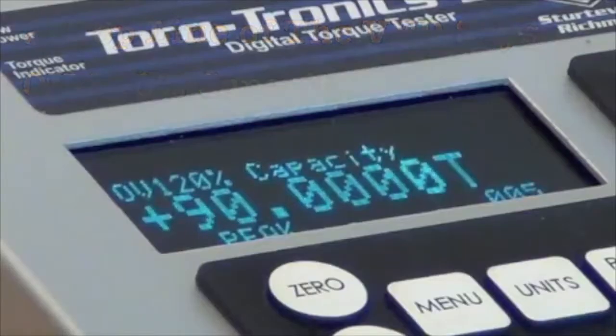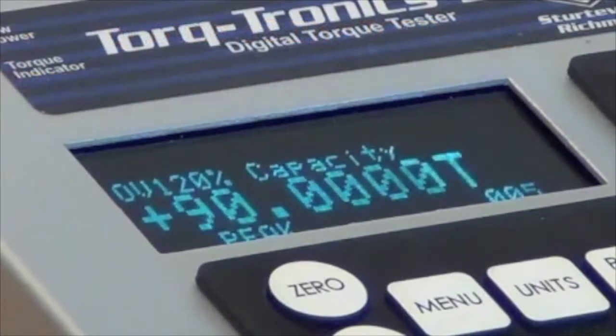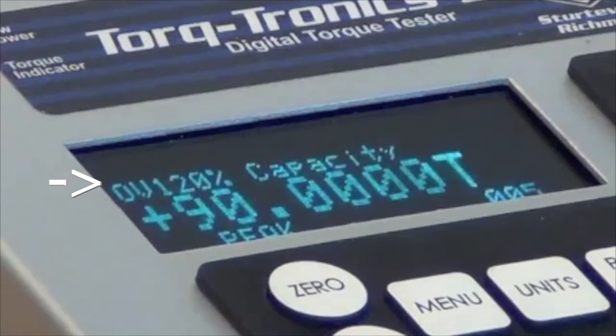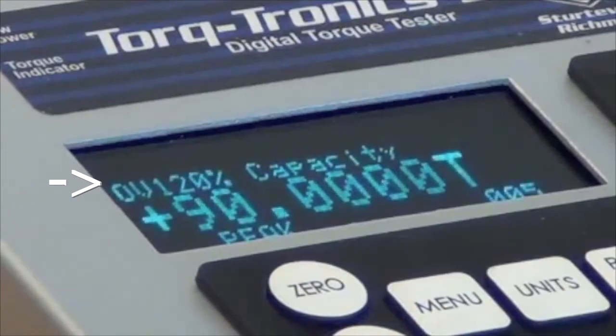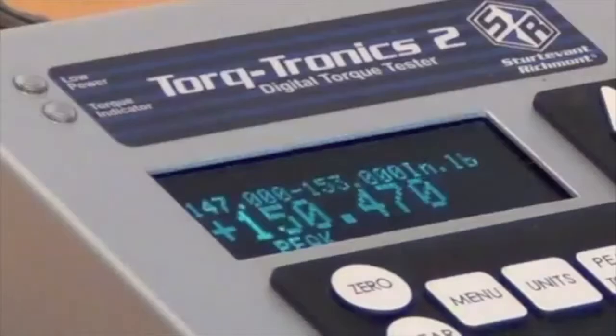If you try and test and calibrate tools between an overload event and resetting the overload flag, you'll notice a couple of things. First, the upper line of the tester display says OV 120%. The lower left-hand corner of the display where you normally see OK or bad, you'll see OV.